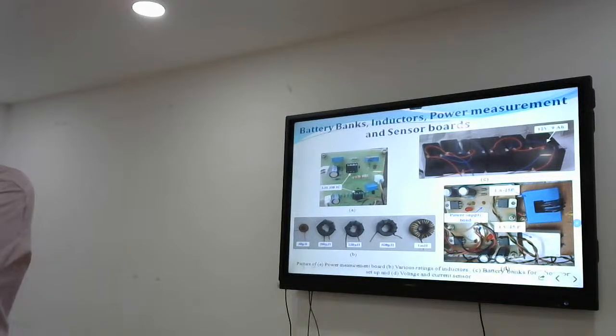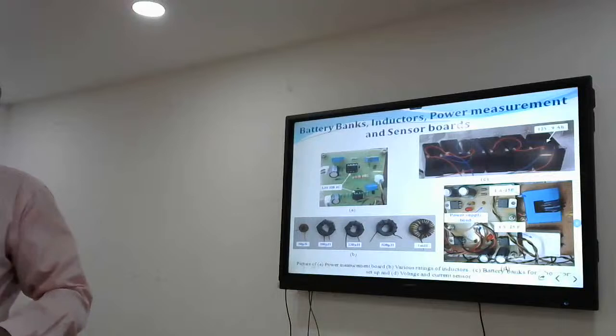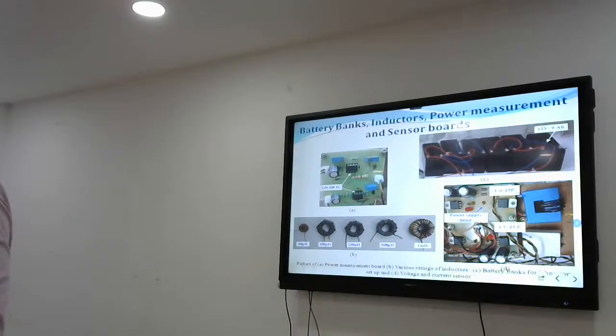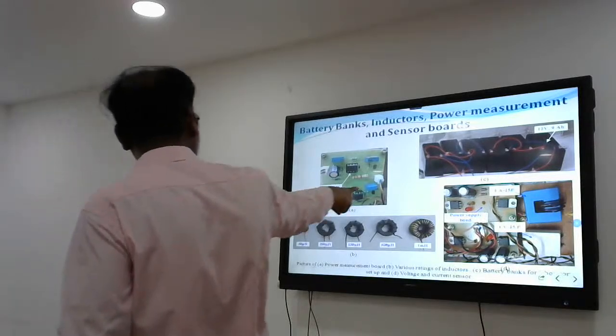It converts with the help of a Hall effect sensor — I think you might have studied this, the Hall effect voltage sensor. Same thing for current: 100 ampere will go, but you cannot divert 100 ampere into your digital processor — the processor will get damaged. Even if 100 ampere goes, no matter, only 0.5 volt will come out. So 0 to 0.5 variation is proportional to 0 to 100 ampere variation, and similarly 0 to 1000 volt variation. That is our voltage and current sensor, most popularly available.